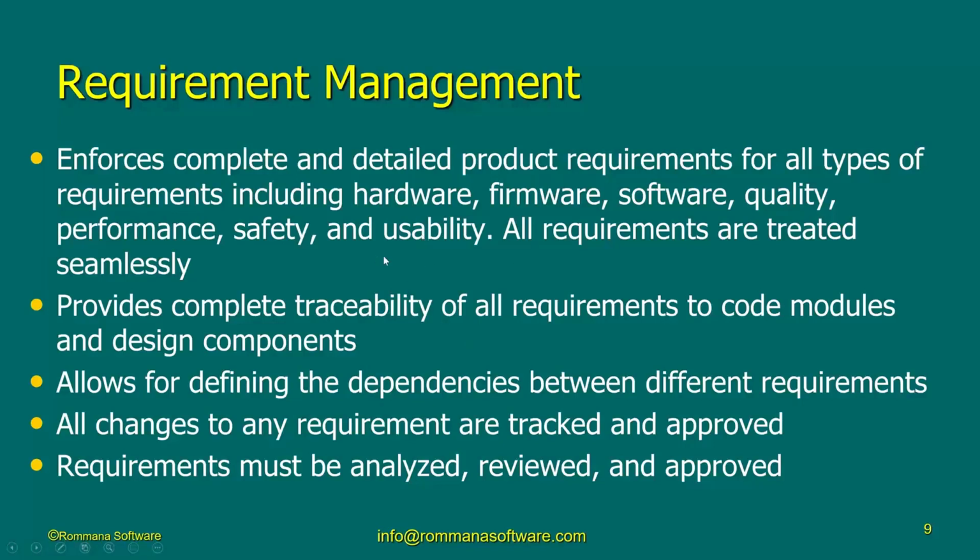So the requirement management process in Rommana ALM enforces complete and detailed product requirements. Okay, if you want to use Rommana ALM for device software, you'll find that you could really do all the documentation you want, and you can document all kinds of requirements: hardware, firmware, software, quality, any performance, and any safety. All these are documented within Rommana ALM with all levels of rigor. Rommana ALM also provides complete traceability of all the requirements to everything else: code modules, design components, test cases, and these are very straightforward requirements by all the standards.